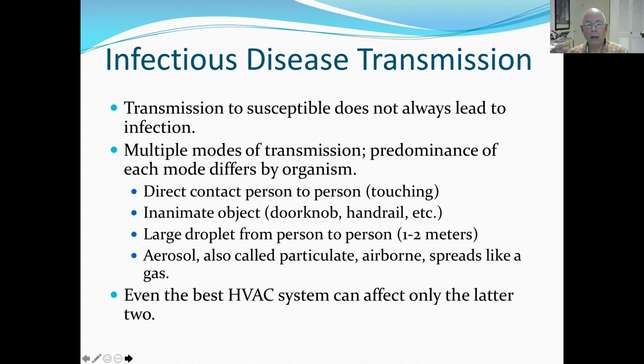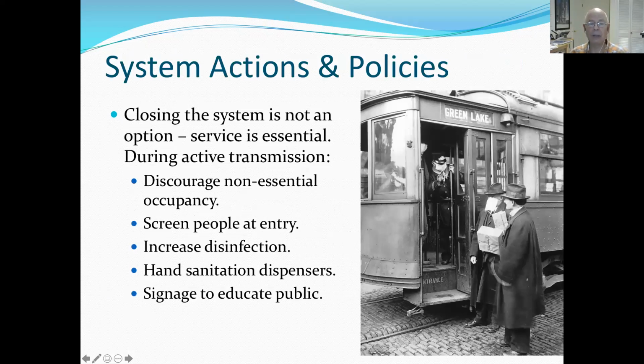My colleague Yugo Lee in Hong Kong makes the point that at 1 to 2 meters, which is 3 to 7 feet, it may not just be a large droplet that goes from me to you. It may be the greater concentration even of those small particles in the cloud, that can spread like a gas at a higher concentration between me and you when we're at close proximity. So the HVAC system can only help for the last 2 bullets. So that's why I say that the HVAC system plays a small role as long as you have a decent one that is not allowing concentration to happen.